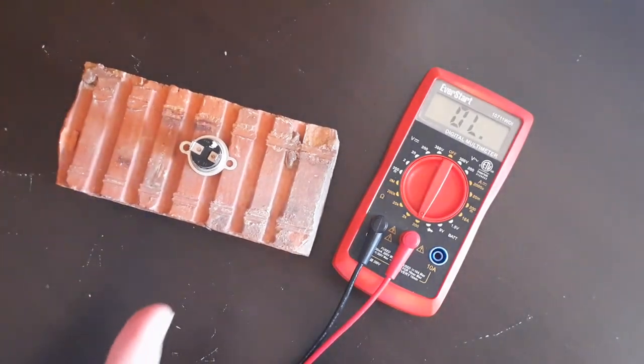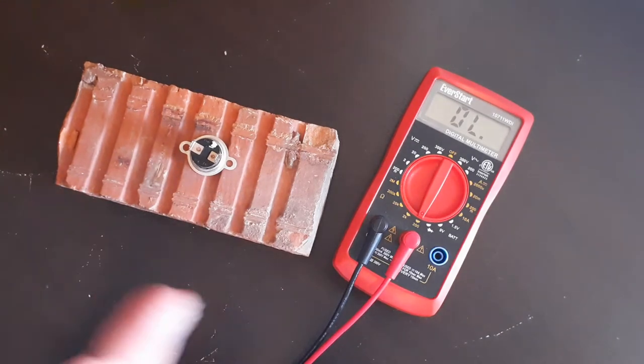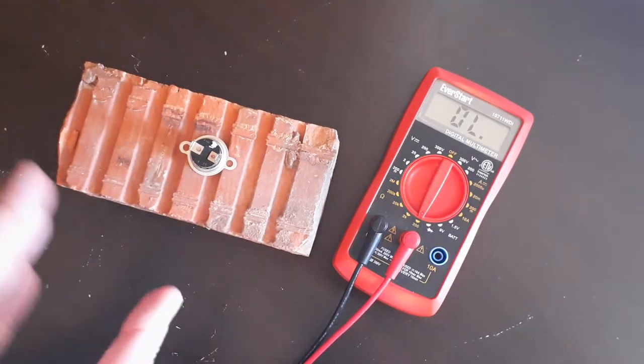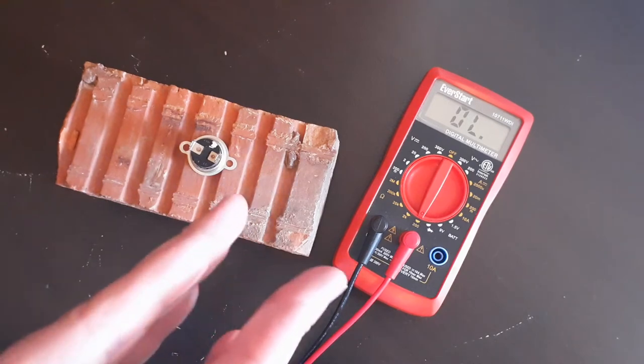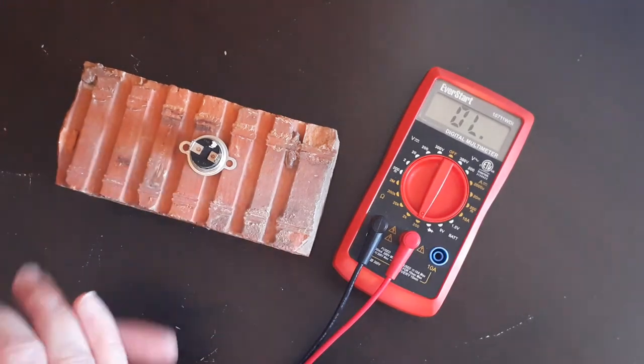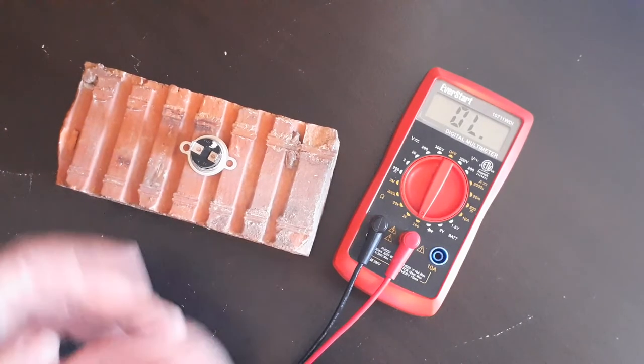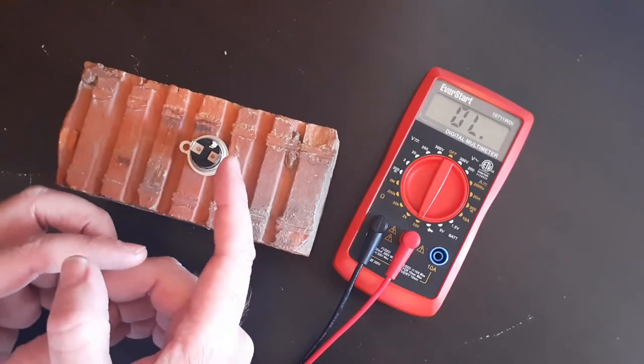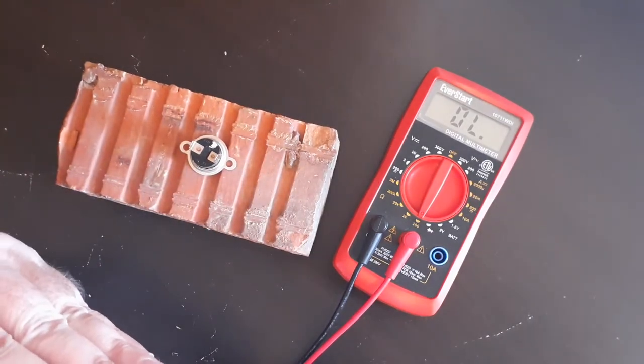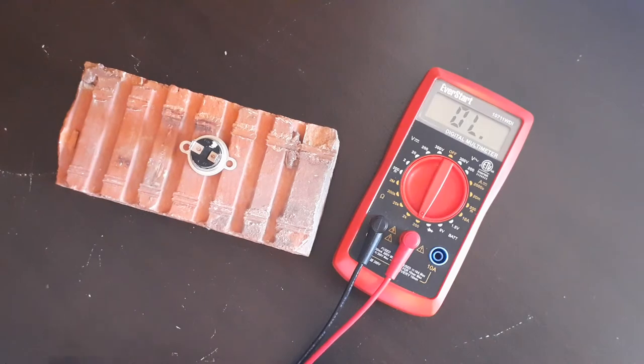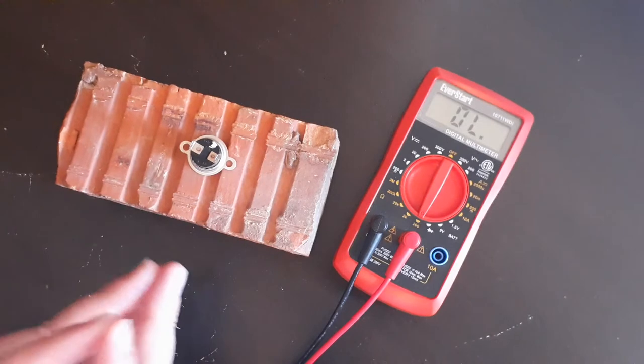When you initially test a thermostat before heating it up, when you initially touch the leads of your multimeter to the thermostat and it changes from OL to any number—even if it's 0.00—that means the lines inside are closed and they are touching each other and providing some kind of reading from one side to the other. Means they're closed.